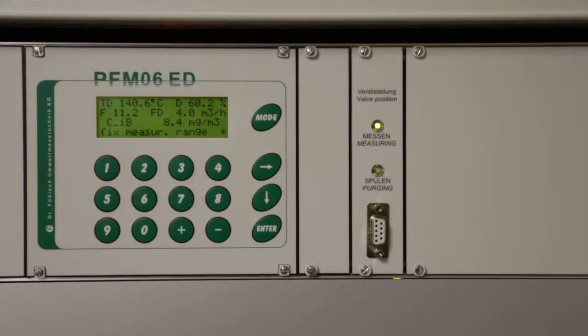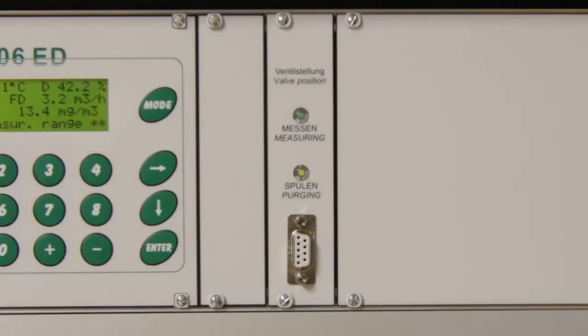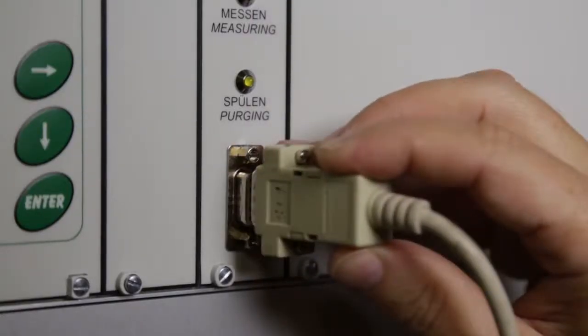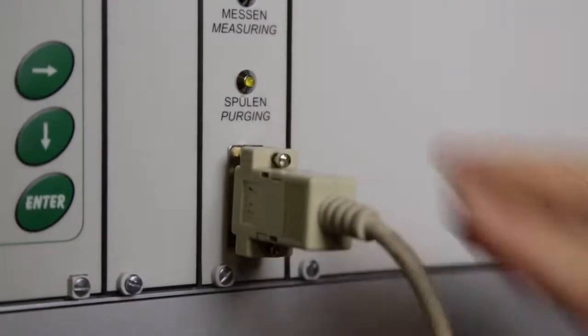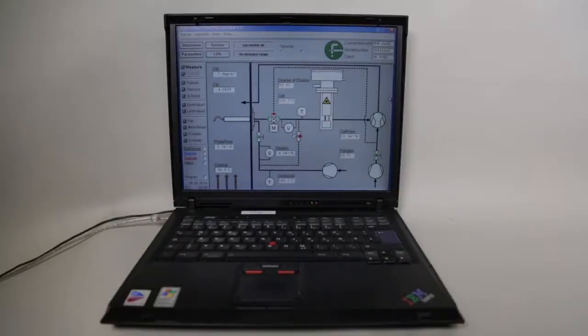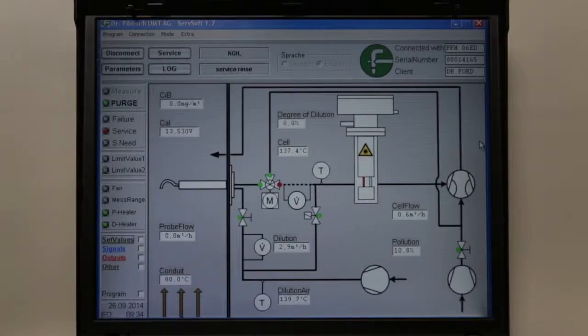The measuring system shows its current status at the LEDs measuring and purging. If the control unit is connected to a PC via serial RS232 interface, the service software displays all measuring values and calculated values clearly. You can also save all settings and messages directly at the PC. The PFM 06ED works fully automatic. There is no necessity to interfere manually.